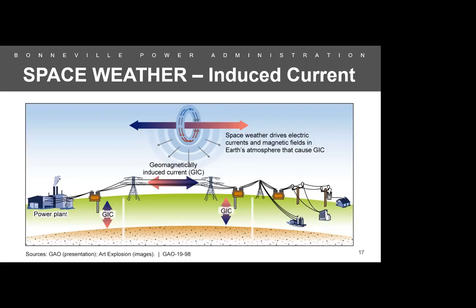Fortunately, we haven't been significantly damaged by geomagnetic induced currents. Since 1964, when the 500 kV grid started, end-use electric power has grown from 650 billion kilowatt hours to 3.7 trillion kilowatt hours, an increase of 465%, with the 500 kV grid carrying 86% of that load. The high voltage grid has grown from about 30,000 to 160,000 circuit miles, a 433% increase since 1964. This suggests grid margins are being reduced because the base load delivered by 500 kV transformers is increasing, but the growth in transmission paths isn't keeping up.